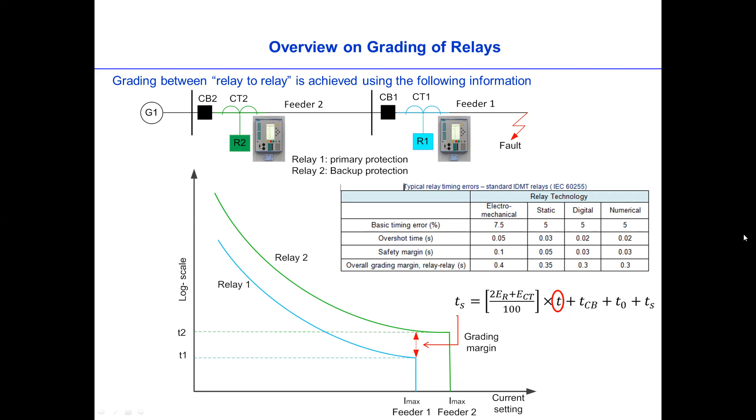If you look up on this one, the T itself is the trip time of the relay. For example, trip time at minimum fault level. So which one is the minimum fault level? Well, this will be the fault level at the end of the network because that's the fault level at minimum.